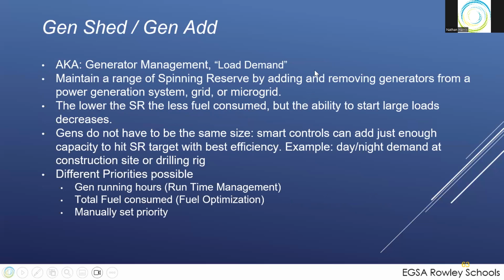Gen Shed Gen Add is also known as generator management, and some call it load demand. I put that in smaller font on purpose because that's not a good term to me, but some use that term. It's the idea of adding and removing generators from a power generation system in order to get the right amount of spinning reserve and optimize your fuel efficiency. So it's adding and subtracting generators as needed to maintain a certain spinning reserve.